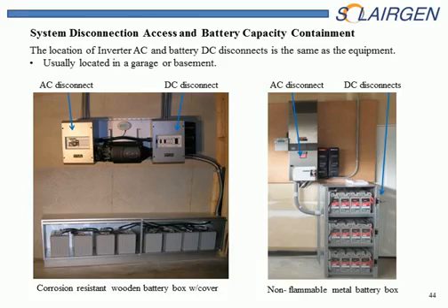What's the big hazard? Well, the batteries, if they're flooded, if you were to spray enough water on them to cover the terminals, which are usually 12 inches above, then you could have a shorting and they could melt down and cause a fire. Lead acid batteries are not very prone to do that. They don't discharge current that quickly. Lithium ion batteries are a different story. And of course lithium ion batteries are expensive and they're just now really hitting the market, so I think they will be covered by a lot of safety features.